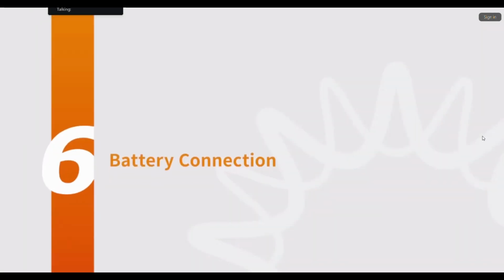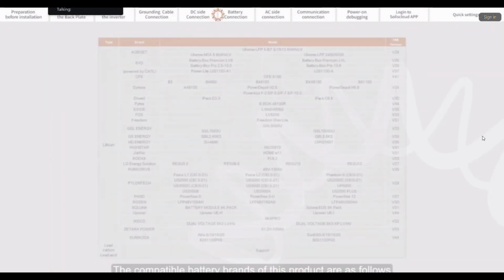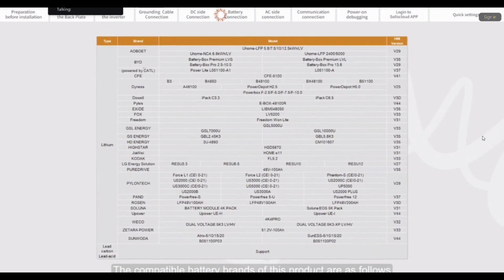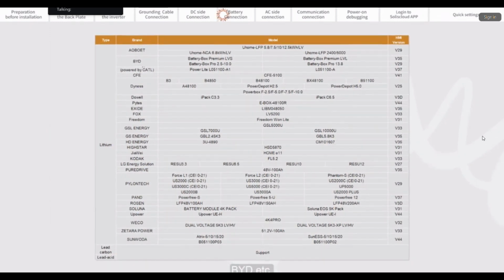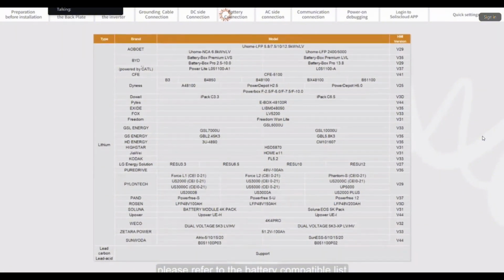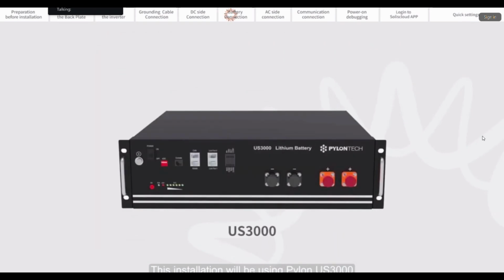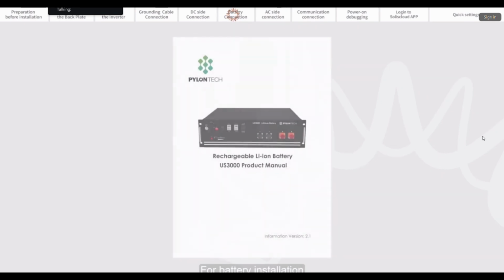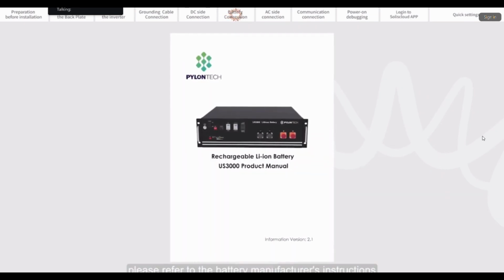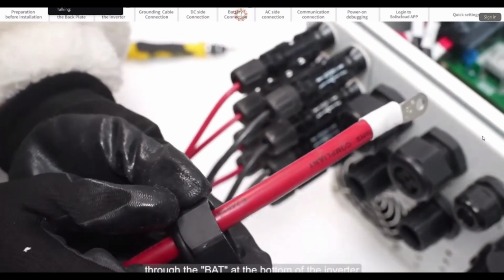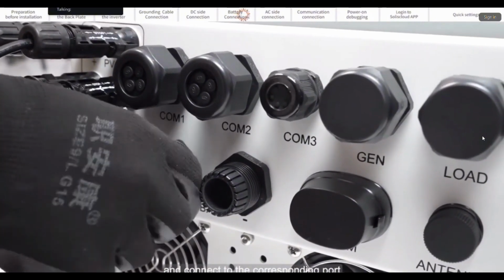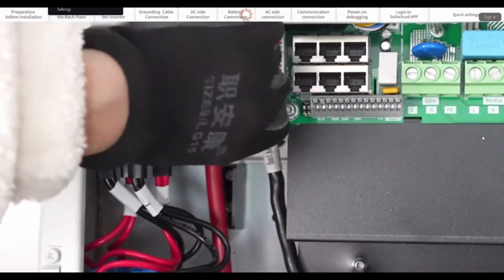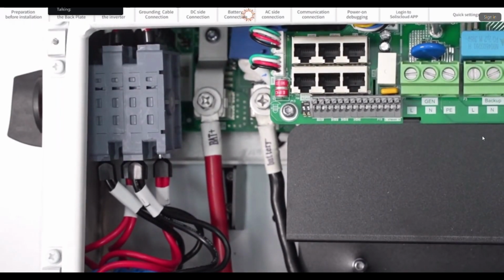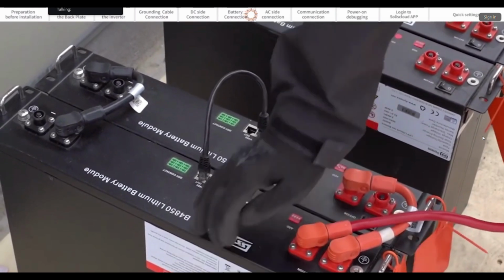Part 6. Battery connection. Compatible battery brands of this product are as follows: Pylon, BYD, etc. Please refer to the battery compatibility list on the Solis website for details. This installation will be using Pylon US 3000s. For battery installation, please refer to the battery manufacturer's instructions. Pass one end of the battery power cable through the BAT at the bottom of the inverter and connect it to the corresponding port. The other end is connected to the battery.